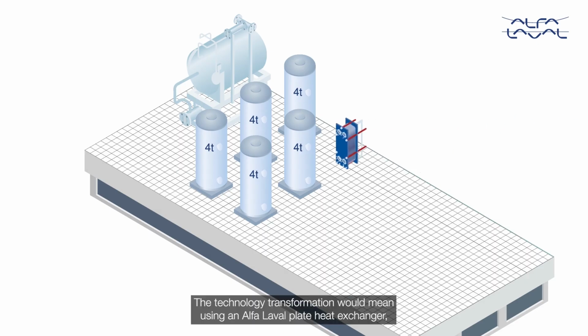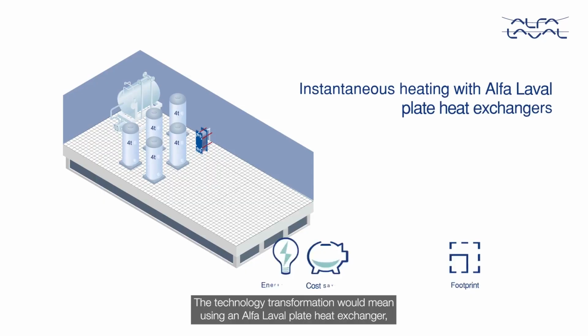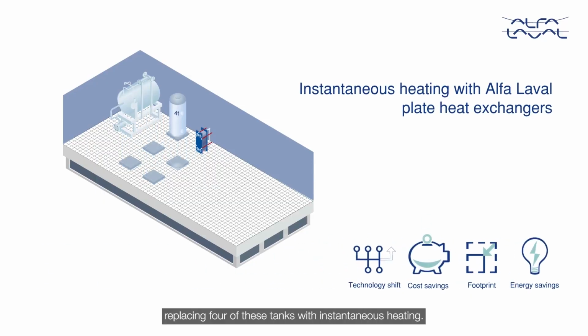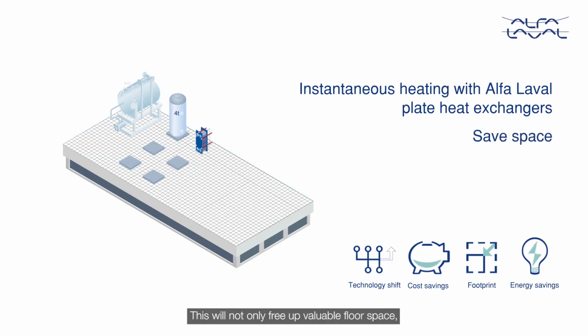The technology transformation would mean using an Alfa Laval plate heat exchanger, replacing 4 of these tanks with instantaneous heating. This will not only free up valuable floor space, but provide lifelong savings in fuel costs. One tank is kept for hot water needs for unusual hours, preventing unnecessary boiler fire-up.